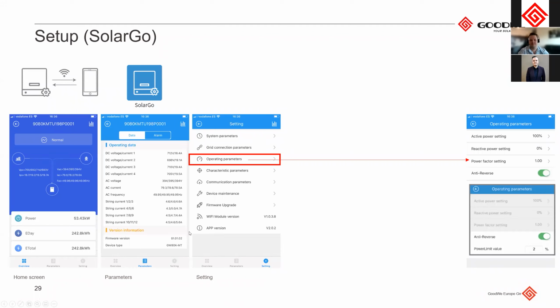There is one other thing that I am missing in my slide, which is the communication parameters. As you'll see, we have our communication parameters. We have to go into the communication parameters and select the COM address, so the communication address of our devices. When we have our devices connected to the SEC1000, we need to make sure that our devices are numbered from 1 to 60. The default you'll see is 245, or 247 will be the default that they're on. If we do not change this, even if we only have one inverter, the SEC will not be able to issue commands to our inverter. So we need to make sure that the communication address for the RS485 is set in the proper range, so from 1 to 60.